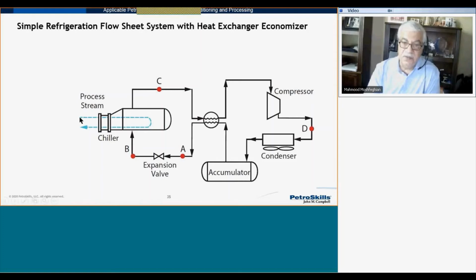So this is a simple refrigeration system. What we did, we added another heat exchanger here to do subcooling. So here we're coming out of the condenser, saturated liquid. We go to the heat exchanger. We cool it down at the cost of raising the temperature of the cold gas out of the chiller. So what happened when we come through here, pressure goes down, so suction pressure to the compressor goes down, and temperature goes up. But let's follow the path and then come back here. So I'm going in saturated liquid. When I'm coming out, I'll be at point A subcooled because I'm cooling down saturated liquid.